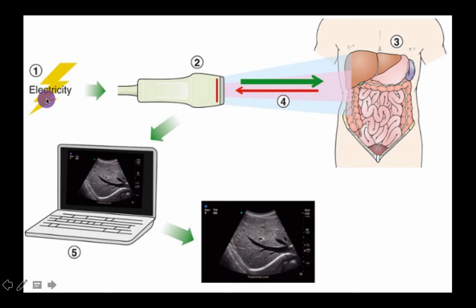The ultrasound machine takes electric current and applies it cyclically to ceramic materials or crystals in the head of the ultrasound probe to make them expand and contract, which results in vibration. This is known as the reverse piezoelectric effect. Piezo meaning squeeze in Greek, so we're using electricity to squeeze the crystals. This vibration generates sound waves. This is the emission phase. The sound waves are transmitted to structures in the body. Some of these waves bounce off structures they encounter and return to the ultrasound probe. The returning sound waves make the crystal vibrate again. This is the listening phase. This vibration is converted into an electric signal. This is the piezoelectric effect. This electric signal is converted into different shades of black, white, or gray, depending on the amplitude of the returning ultrasounds. And the sum of all this information is translated into the image displayed on the screen.